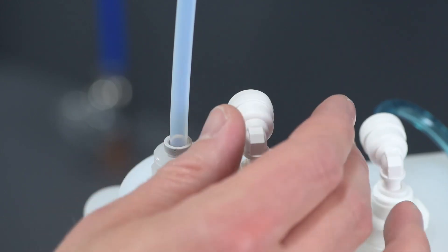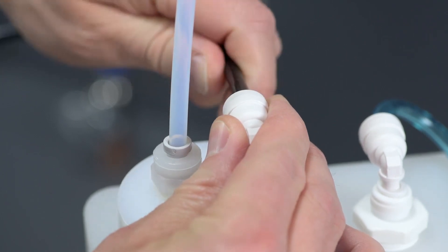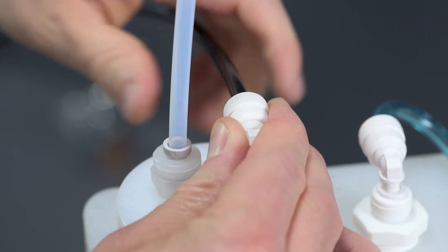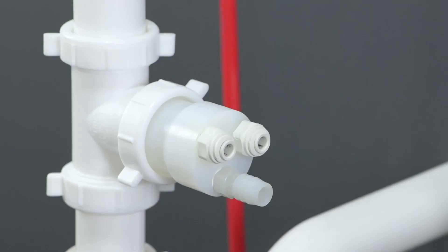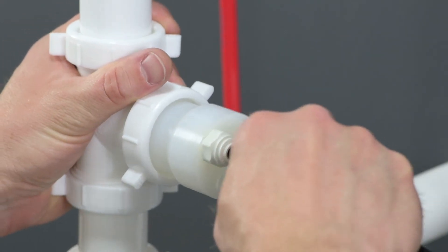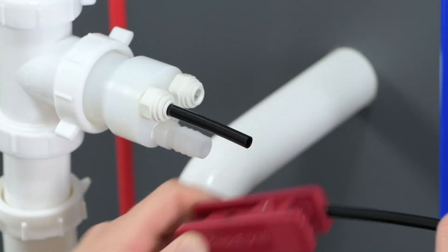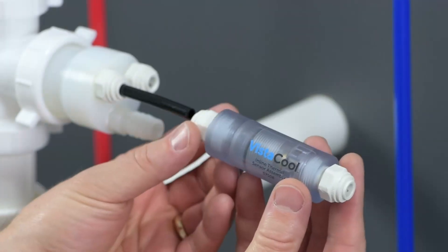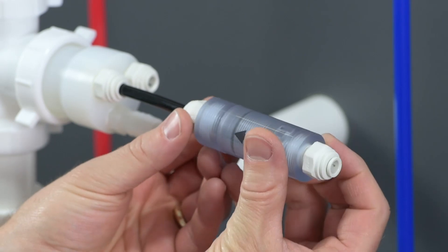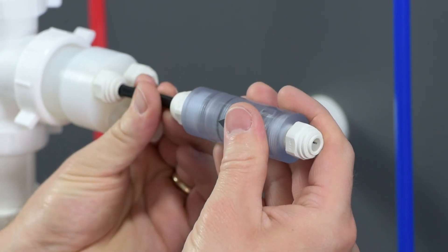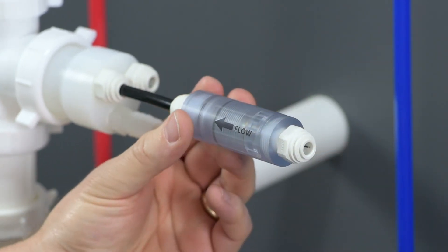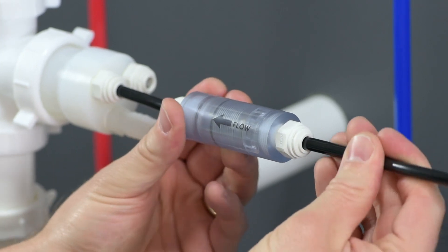Now connect the 1/4 inch black opaque condensate line tubing to the elbow fitting on top of the manifold. Then connect the other end to one of the male adapter fittings on the drain adapter. Cut that same black condensate line as close to the drain adapter assembly as possible and install the inline thermal sensor. Make sure the flow direction on the inline sensor is oriented toward the drain.